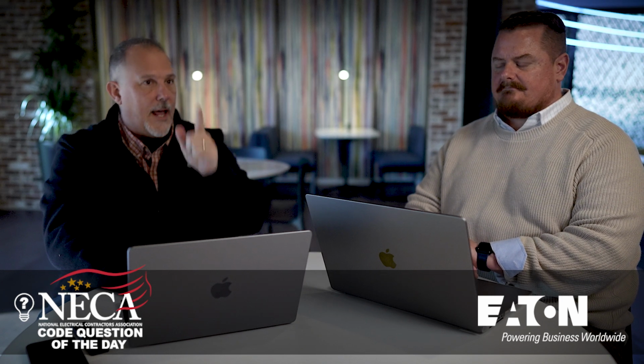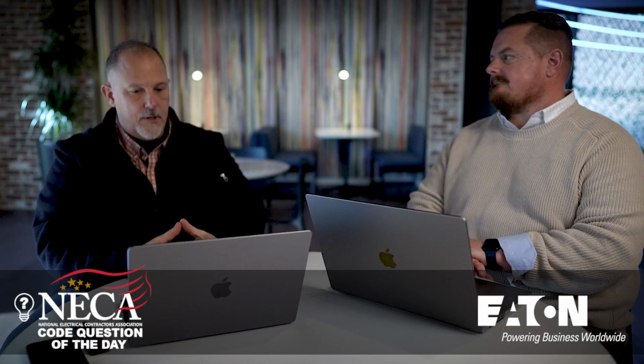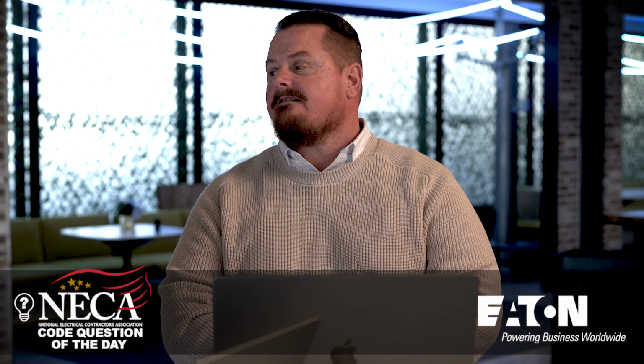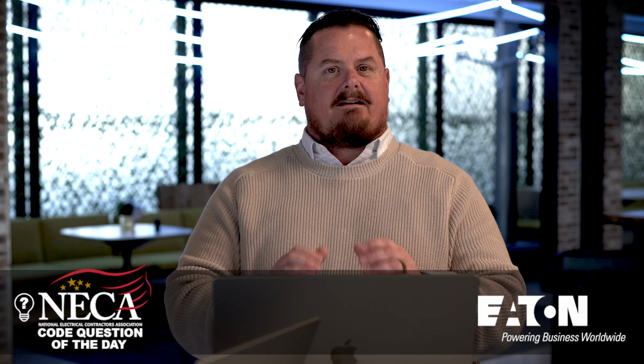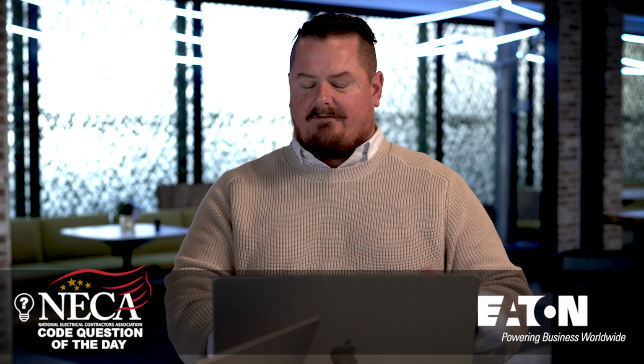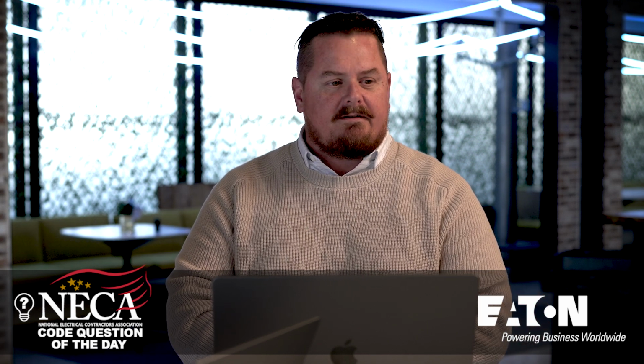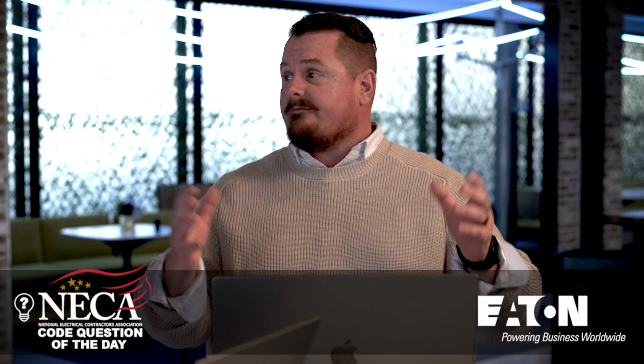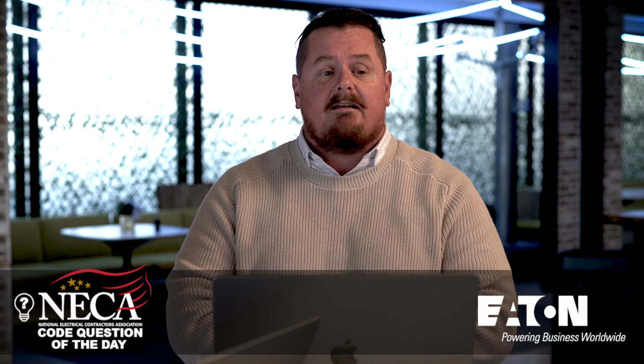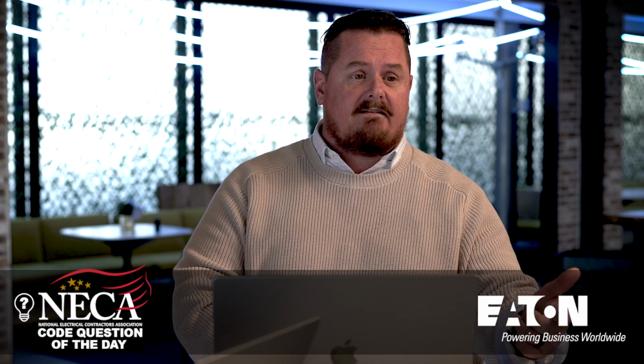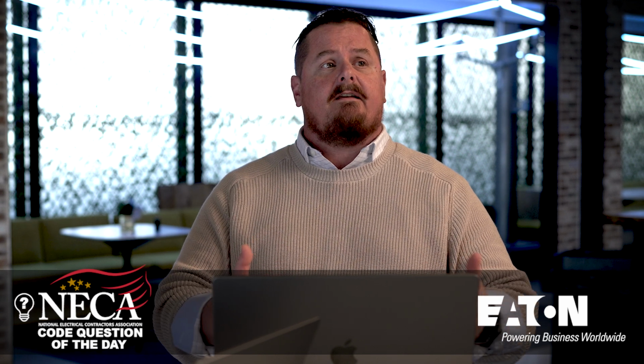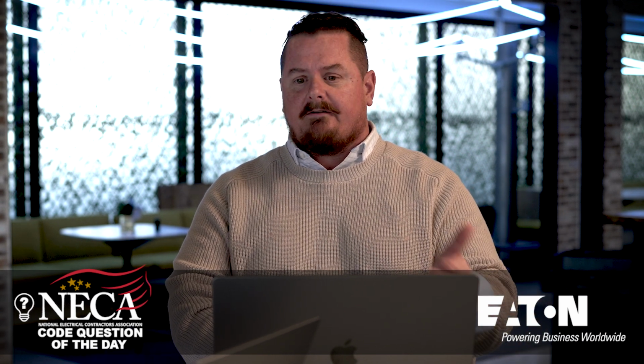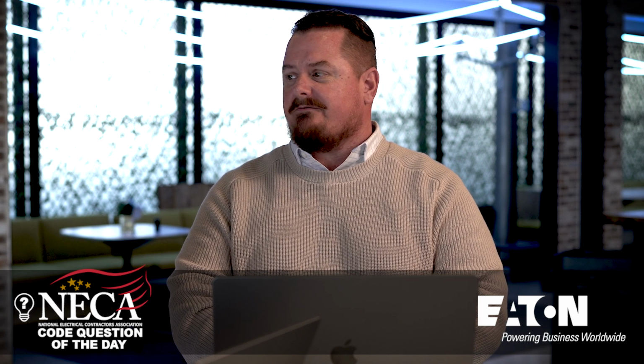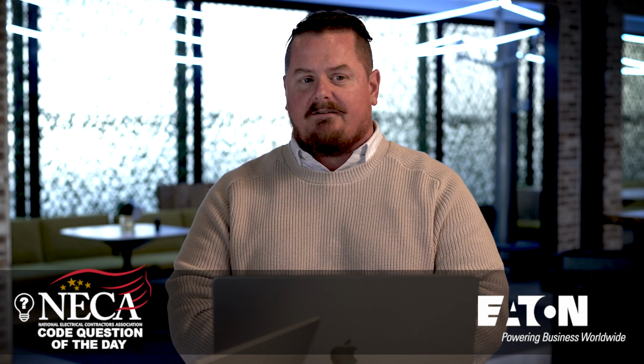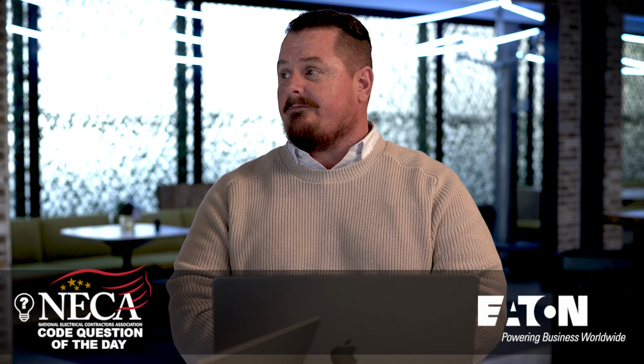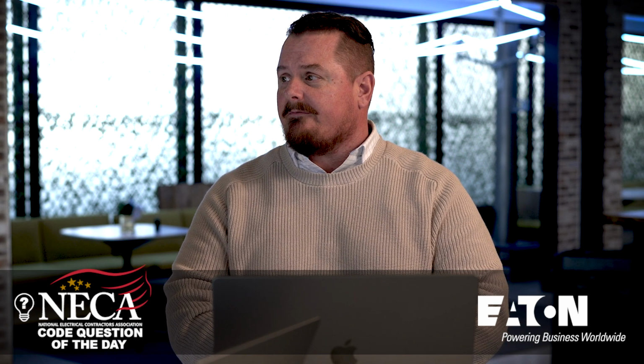Now you had mentioned, in the answer to this question, collaboration. Oh yeah, collaboration. As soon as I see the acronym HVAC in a question, I know the road we're going down. You've got to ask the questions. If you're the one designing these systems, or the contractor installing them, or both, as in design-build, which is a lot of times the case, you have to ask the questions. You have to get with the GC and the mechanical contractor and find out, hey, I need the specs on the HVAC equipment that you're installing, so you can confer ahead of time and not be caught in a situation where you're trying to get a certificate of occupancy and you've got 3 HVAC rooftop units that are not properly rated for what they're going to be exposed to.